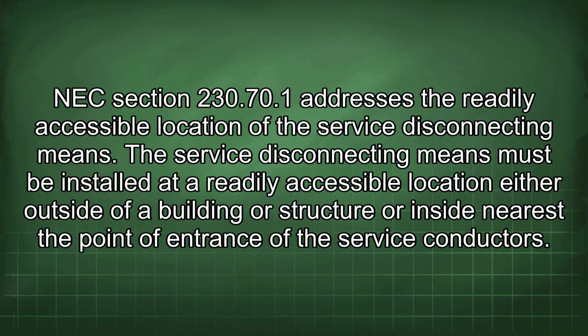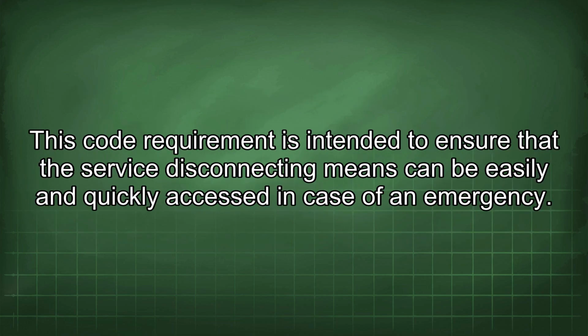NEC Section 230.70.1 addresses the readily accessible location of the service disconnecting means. The service disconnecting means must be installed at a readily accessible location either outside of a building or structure or inside nearest the point of entrance of the service conductors.